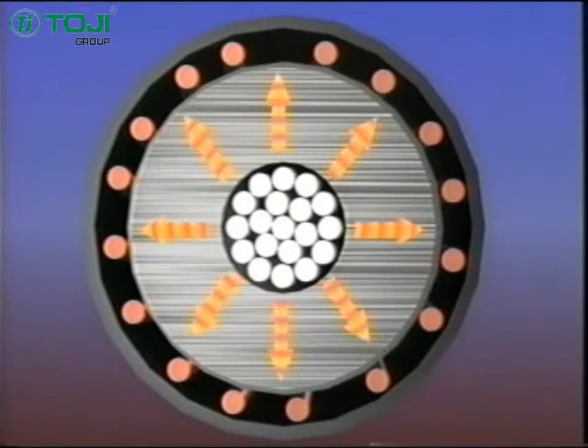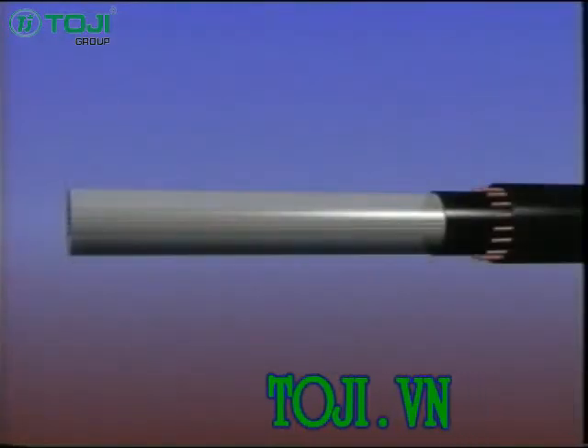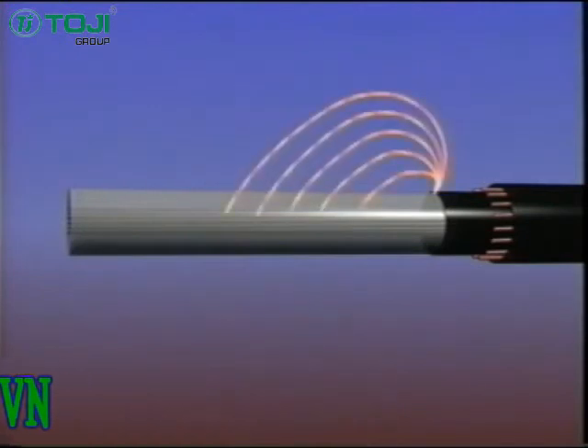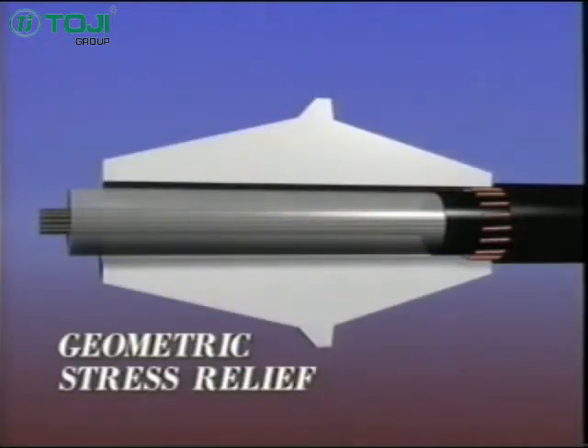The shield around a cable is designed to give a uniform field around the cable conductor. When a cable needs to be terminated, the shield comes to an end or is terminated. This creates a concentration of electrical flux at the end of the shield. All of the flux lines try to flow to the end of the shield. This creates the stress that can be so damaging to cable insulation. There are 2 methods for relieving electrical stress.